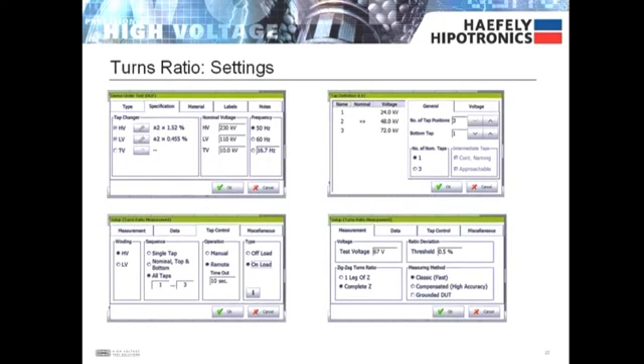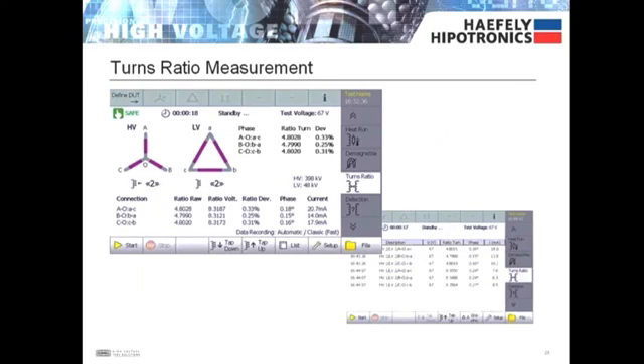During the turns ratio mode, the user enters information on the tap changer, nominal voltages, which taps will be tested, ratio deviation threshold, and much more. When the turns ratio measurement is complete, all data is displayed: turns ratio, its deviation from nominal, as well as voltage ratio, phase displacement, and excitation current.